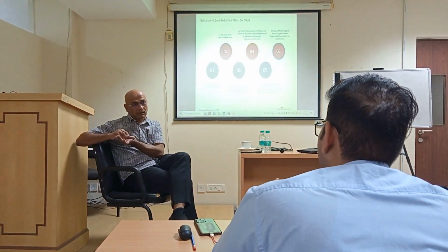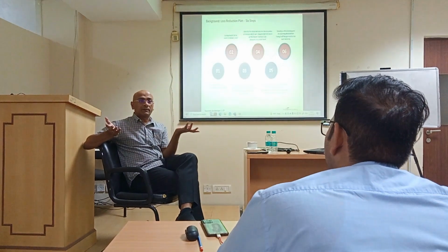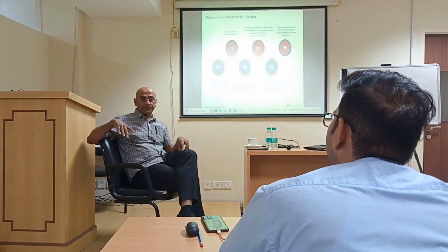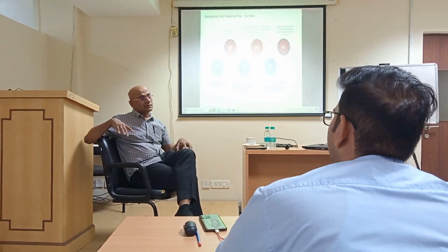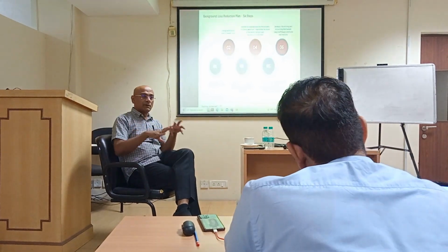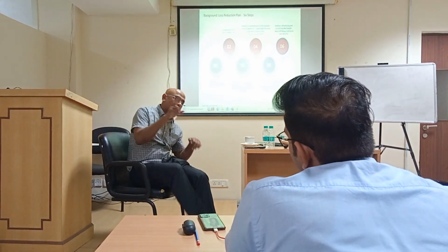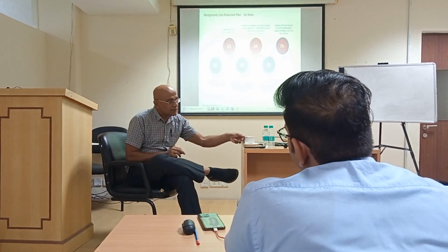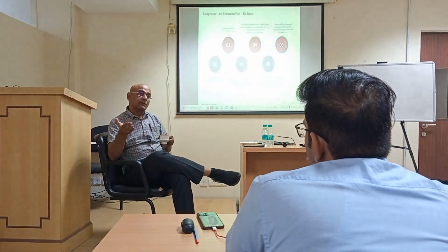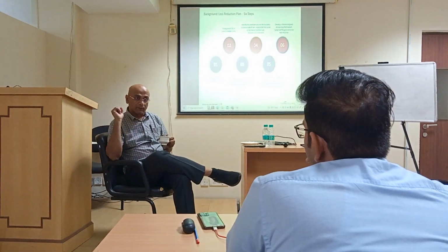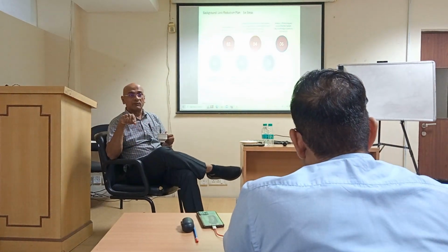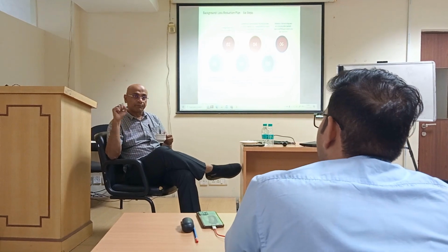Was it similar to an energy audit? Yes, you cannot do an energy audit without meters. So we said, okay, let's take some pilot. Energy audit people first meter everything. So we put 11 kV feeder meters. We took 1 or 2 11 kV feeders. In that 11 kV feeder, whatever number of transformers, some has 10, some has 15, we put meters on the transformer secondary as well.